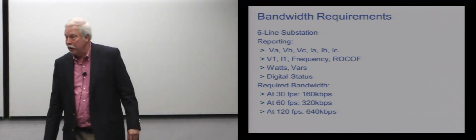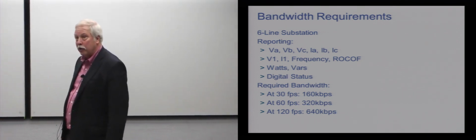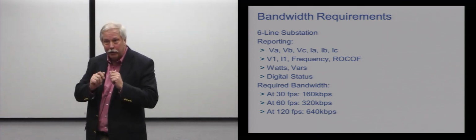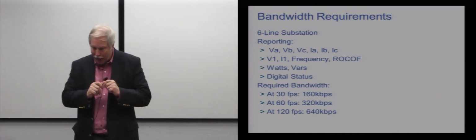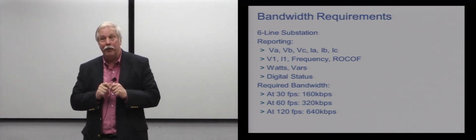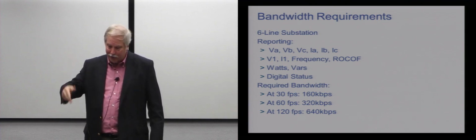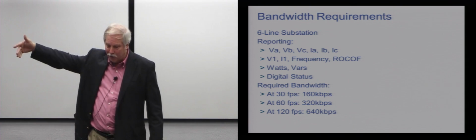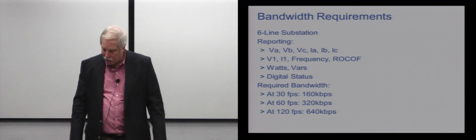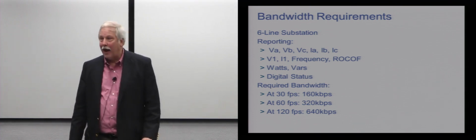In this case, the frame rate dictates the bandwidth required. So if I'm sending measurements from my substation at 30 frames per second, and I'm sending VA, VB, VC, you see the list there, IA, IB, IC, V1, I1, frequency, etc., I need 160,000 bits per second of bandwidth on my communication channel.